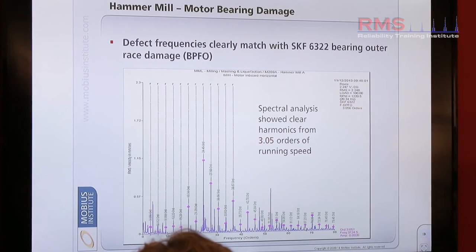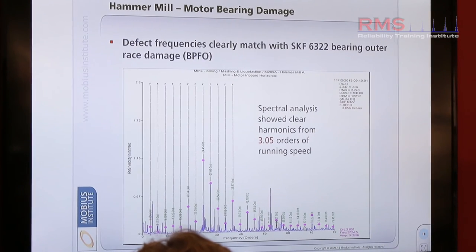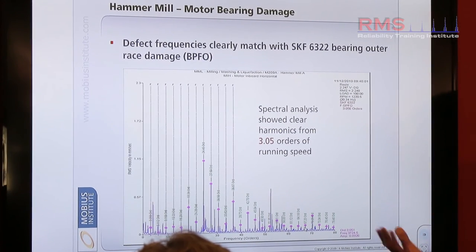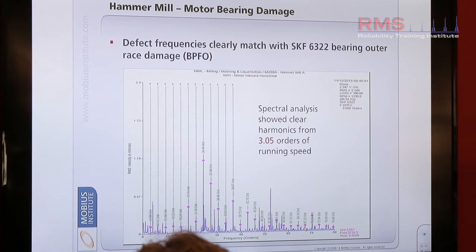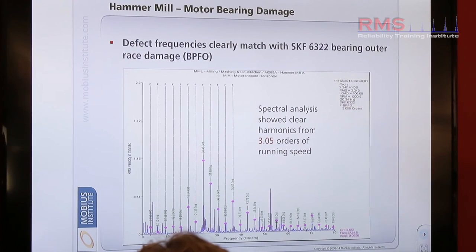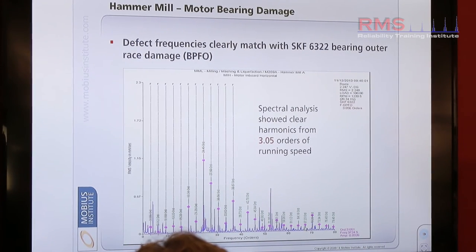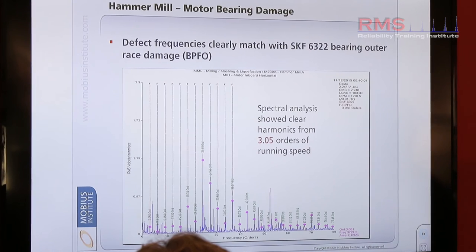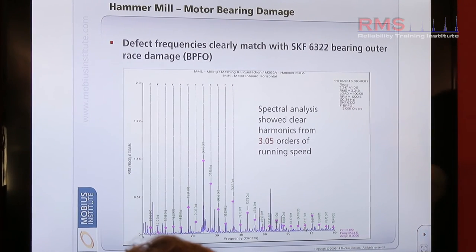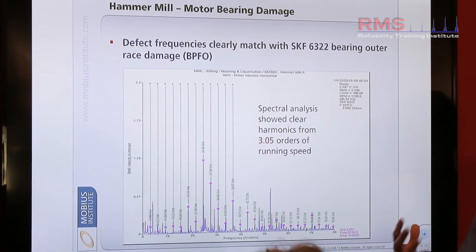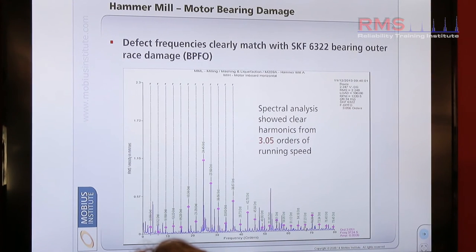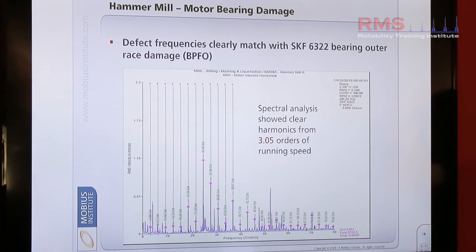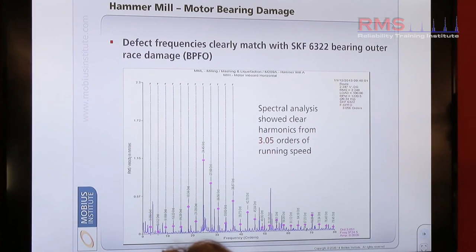Some might think we don't have the bearing number in all cases — not a problem. What else could cause 3.1 shocks per rotation on a grinder and a motor? Apart from transmitted vibration from somewhere else — which it wasn't, because it was only present at the motor — electrical vibration could cause a strange number here. Well, it wasn't that. It had to be a bearing. So we would have known anyway.